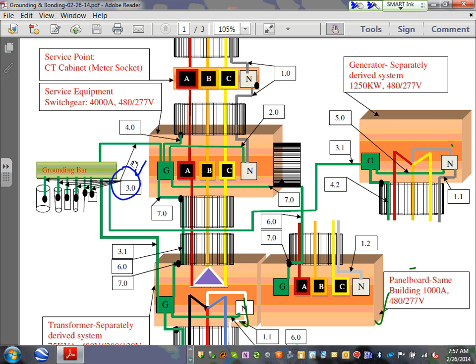So you bring a wire to the ground bar, that ground bar here on the wall, and from the ground bar you have to go to these systems here. What you're looking at, guys, are called grounding electrode systems. What the heck is a grounding electrode system? It's defined by the NEC code book as a metallic object in direct contact with Mother Earth. One of them, a ground rod, is one of them. Ground ring, metallic water pipe, concrete encased electrodes, the foundation of the building that has steel in it, that's qualified. Beams, concrete beams, steel beams in direct contact, that's a grounding electrode.